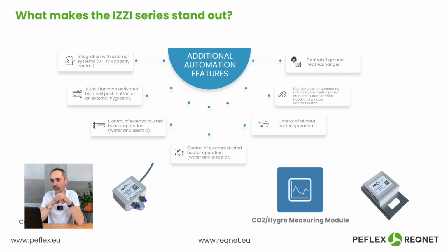The use of CO2 and humidity measurement modules, as well as cooperation with external CO2, humidity modules, or a constant flow module. And when a measurement module is installed, we can also enable the automatic operation mode in the device, meaning that based on air quality, the device will automatically and smoothly control the recuperator's performance. Or other features, such as controlling the cooler or the secondary heater. Digital inputs for connecting a fire alarm control panel, as well as a fireplace or range hood button, or for controlling actuators and the ground heat exchanger.